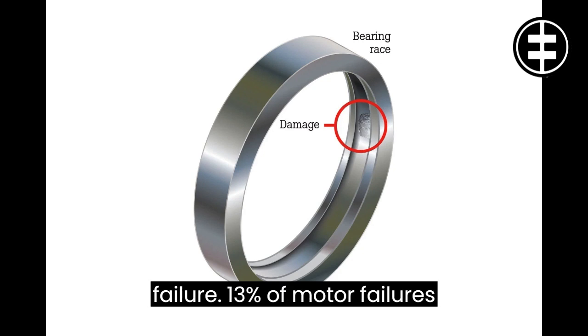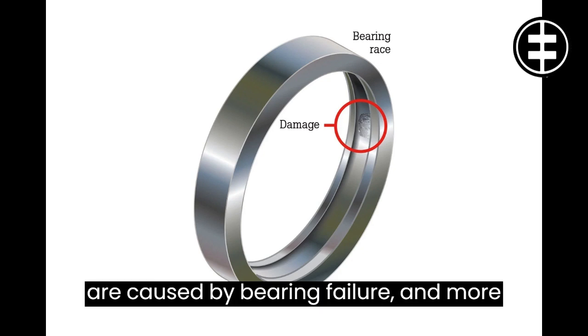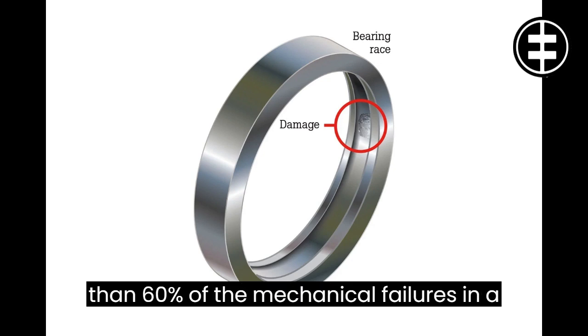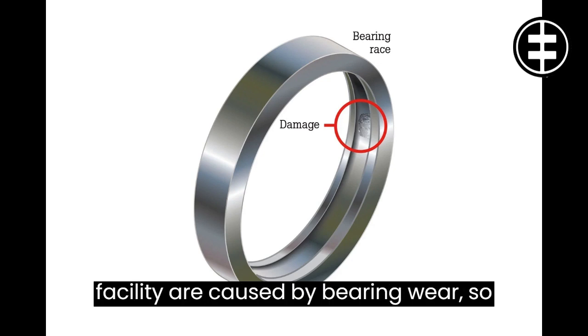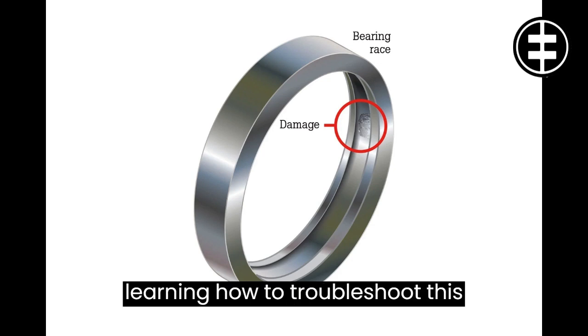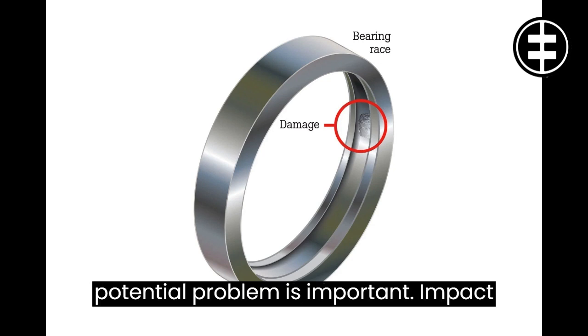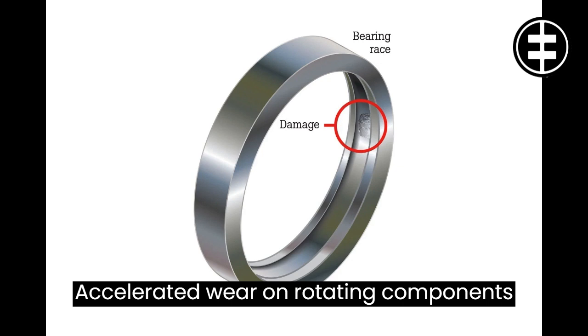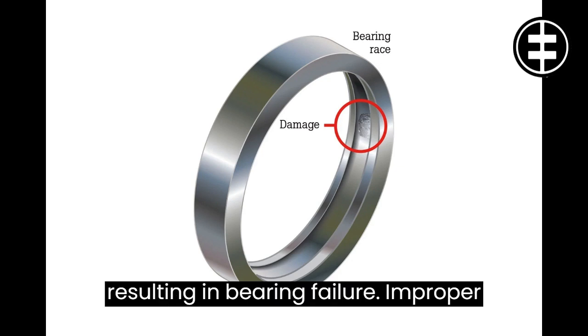13% of motor failures are caused by bearing failure, and more than 60% of the mechanical failures in a facility are caused by bearing wear, so learning how to troubleshoot this potential problem is important. Impact: accelerated wear on rotating components resulting in bearing failure.